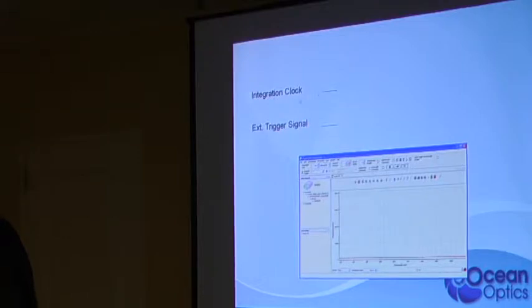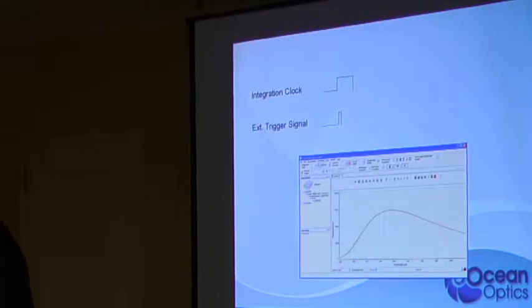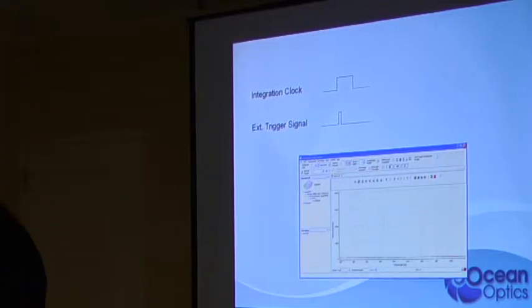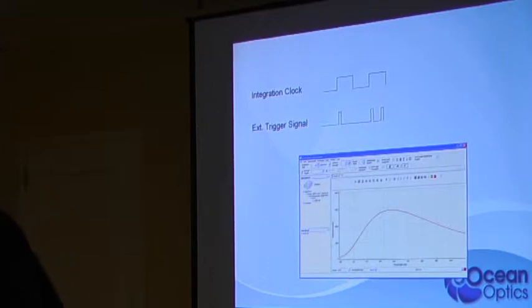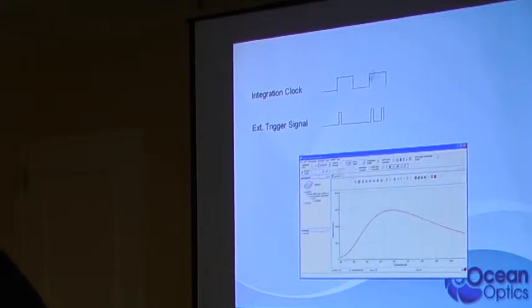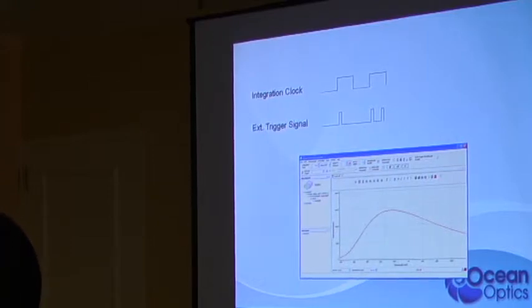Each acquisition takes as long as the integration time. The spectrometer is not acquiring — it's just there waiting for something to happen. I send my trigger pulse, and a new acquisition happens. Then it goes back and waits again: are you sending me another trigger? If not, it stays in standby mode. When you send a new pulse, it wakes up, does its integration time, updates the spectrometer suite, and goes back to standby. If you send a trigger pulse during an ongoing acquisition, it will ignore it until the acquisition is done.